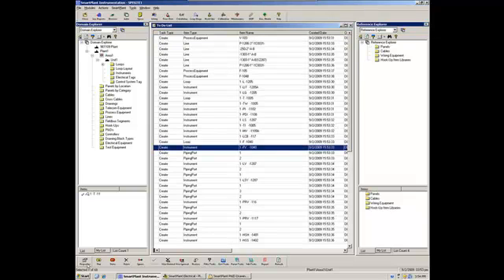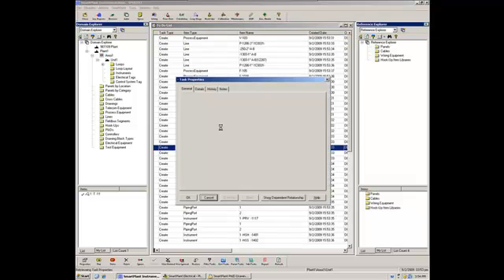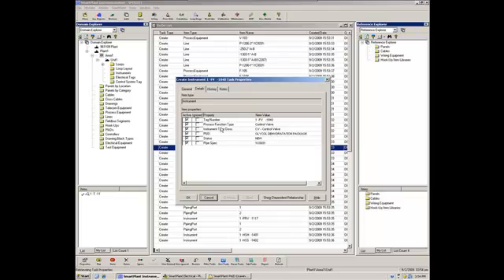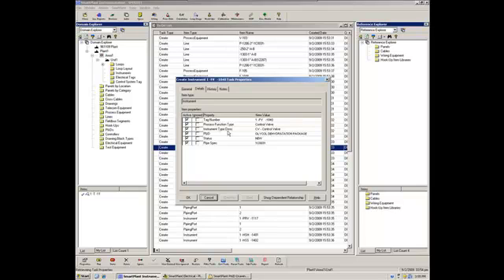If we click in properties, we see all the information that is coming from P&ID, okay? So you see the process function type, there is a control valve, the instrument type, and actually at this stage, when, and we will see this in the standalone demo, when you create an instrument from the scratch in SPI, it uses an instrument type. In the instrument type, you have all the profile of the instrument. If the instrument has a cable, if it has a specification sheet, or if the instrument is located on the field, all that information is taken from the profile. And using the integrated environment, we can do that as well, okay?